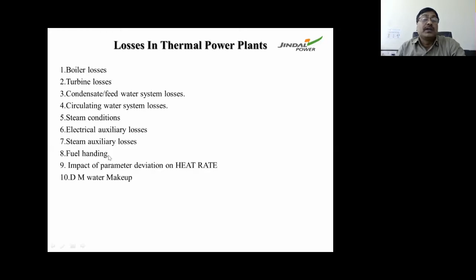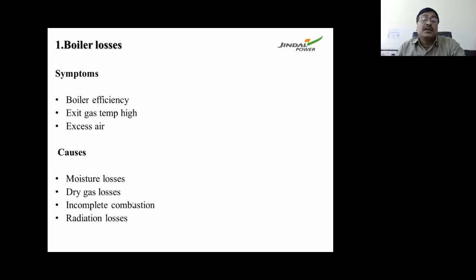If we break down the boiler losses, this results in boiler efficiency. The cause is high flue gas exit temperature and high excess air. Some of the causes for lower boiler efficiency are moisture losses, dry flue gas losses, incomplete combustion, and radiation losses. These are very important to look after, because over a period of time the insulation gets damaged, and it results in heat rate losses which are not closely monitored. We can save a lot if we regularly check the insulation.